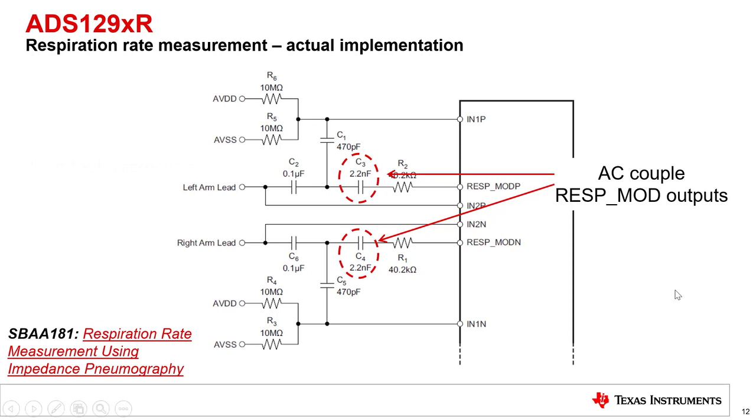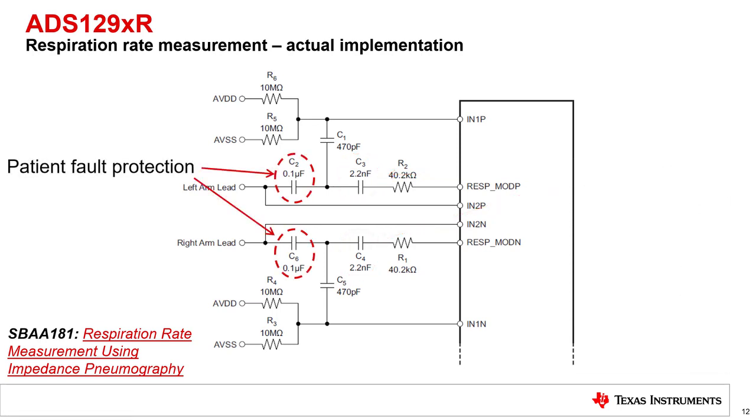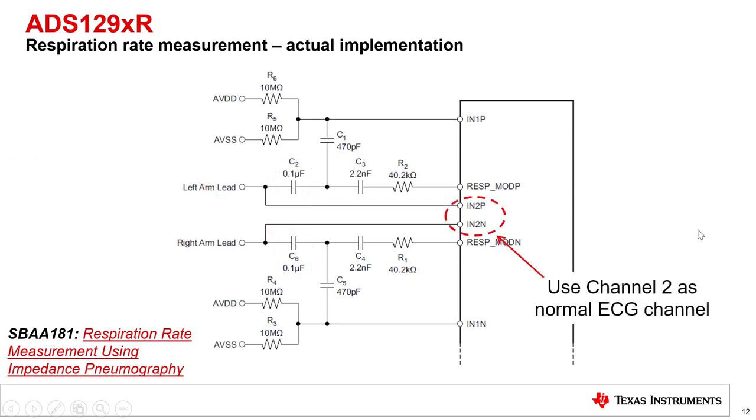Finally, C2 and C6 are added for additional fault protection. The larger patient protection resistors, which are normally used to limit the DC current, cannot be placed directly on the respiration path. The noise from the resistors plus the DC component of the resulting demodulated waveform will prevent the respiration waveform from being resolved.